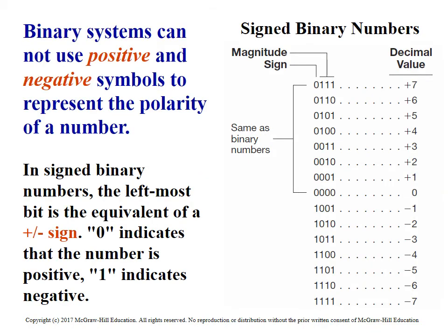Negative numbers. Now that seems a little odd, to have a negative number in a binary sequence. Does it not? Well, the way the PLC operates is it takes that MSB, that most significant bit in a 16-bit or a 32-bit word, and sets that to a 1. Once that is equal to a 1, that value is a negative number. So what that means for us is what? We can't necessarily count all the way up to all 16 bits or all 32 bits.